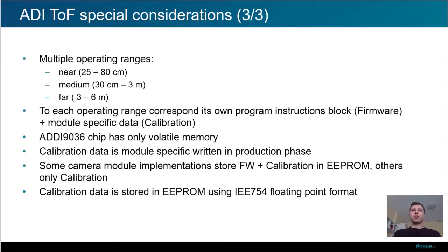So for changing the range, a reprogramming of the volatile program memory of the chip is required. The firmware and calibration data can be stored on the included EEPROM memory from the camera module, but other adopters of the ADI technology opted for storing only calibration on the module EEPROM. We'll see further why this is of importance for the Linux driver.